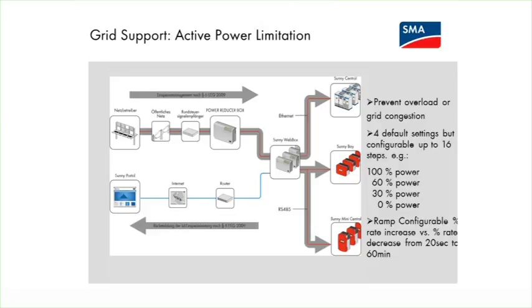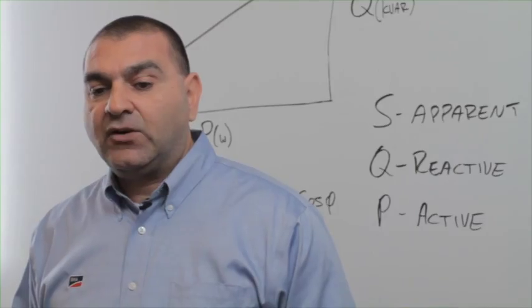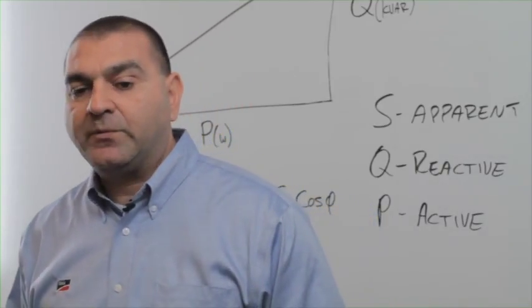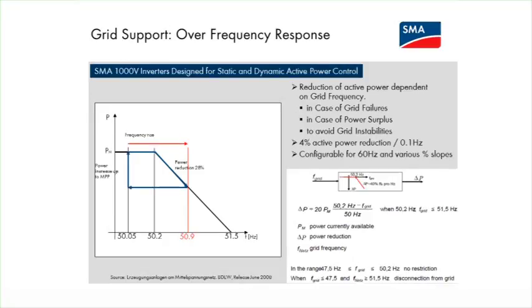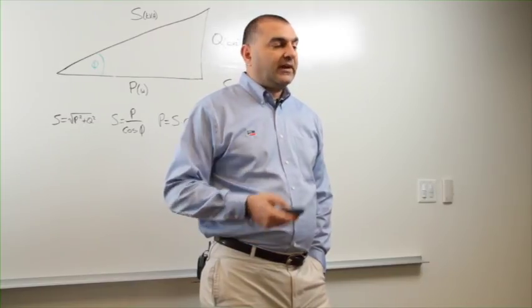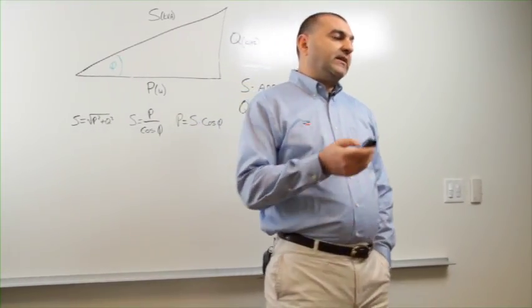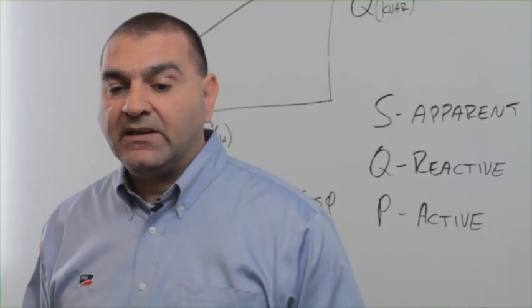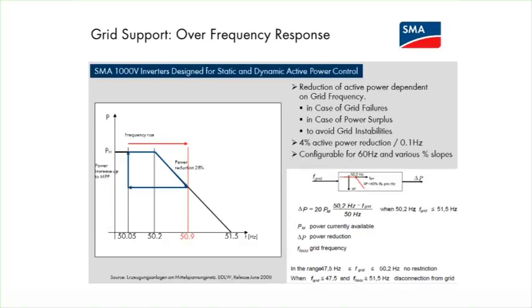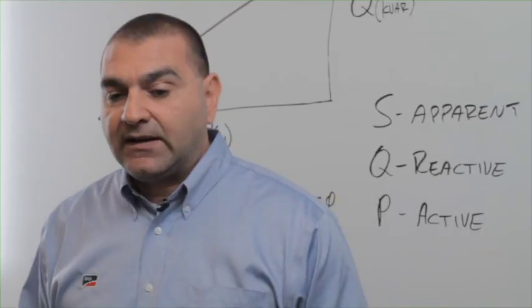The more important frequency feature, which is also a requirement, like I mentioned, in the ERCOT market and other reliability coordination regions, is the automatic over-frequency response. Our inverters are equipped with functionality similar to a conventional power plant, where if the frequency goes higher than a given threshold, in this case maybe 60.5 hertz or 60.4 hertz or 60.2 hertz, whatever settings the utility requires, you can set a percentage droop for every increase of 0.1 hertz on the frequency. The inverter automatically sheds power from its capability. So an over-frequency response is very important because when you have power surplus, grid instabilities, or any kind of grid failures, that comes into play.